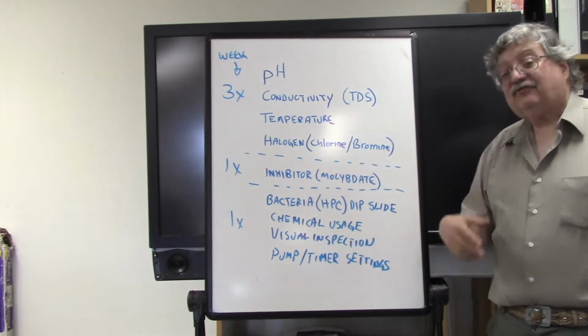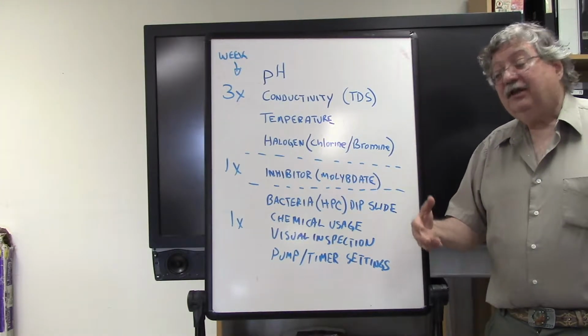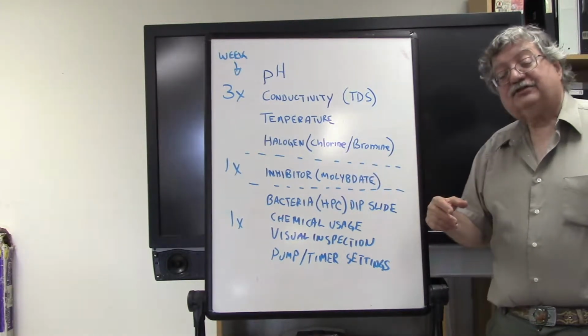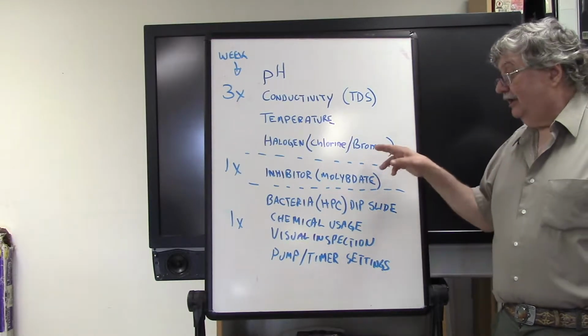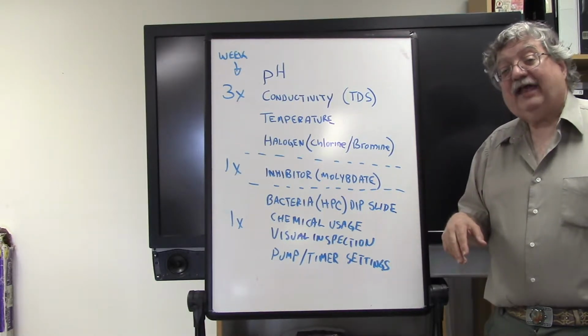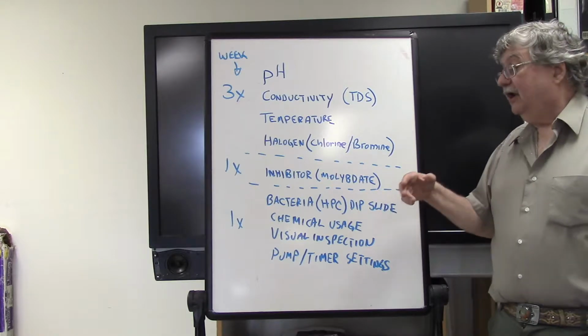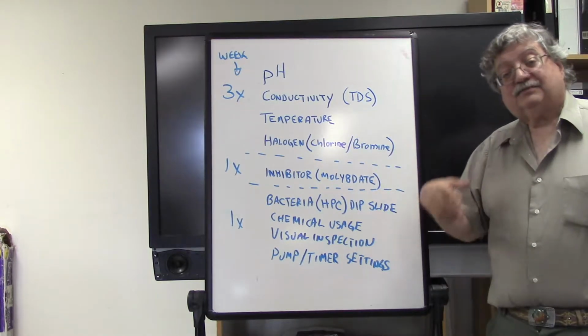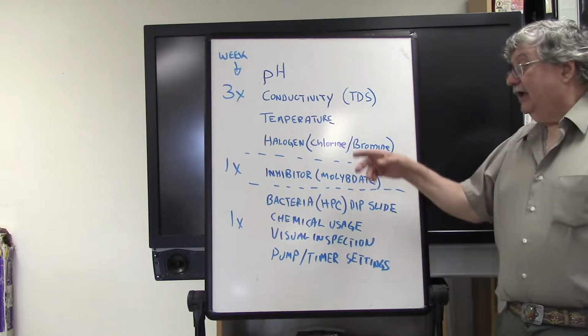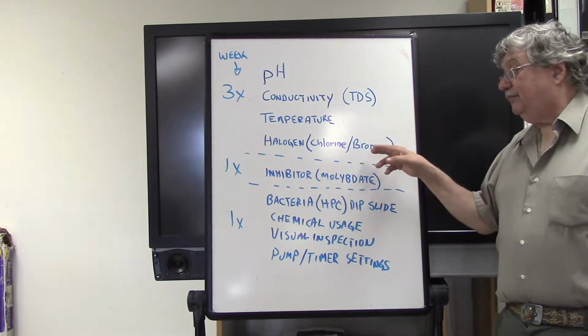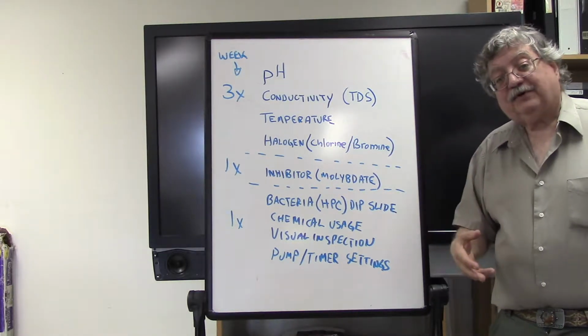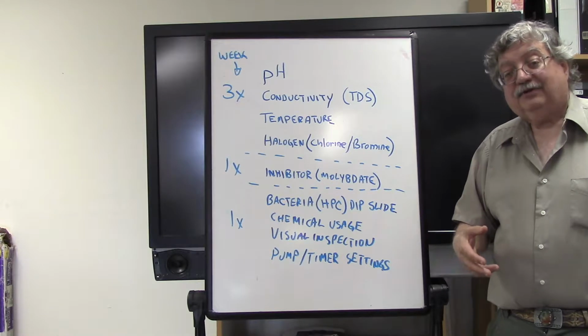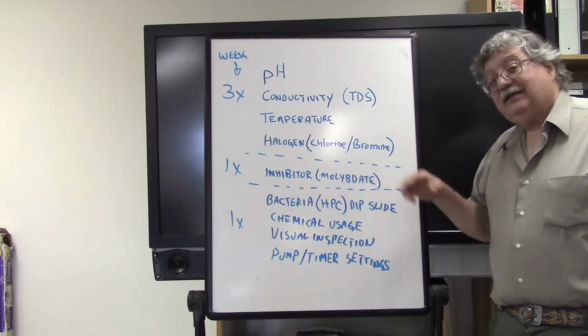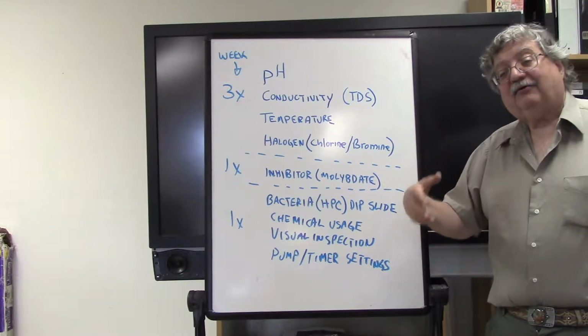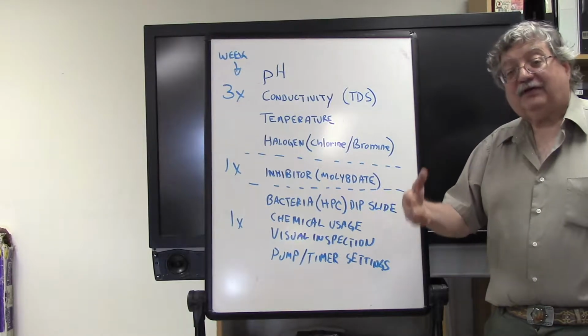You'll also test for halogen, which can be bromine or chlorine. It's just a name for an oxidizing biocide, and it has to feed every day at the same time. You'll test to make sure it's present after it feeds, using the appropriate test kit for your particular treatment chemical, within about a half hour to an hour after the chemical has fed.